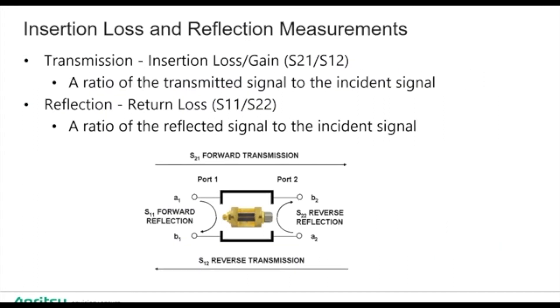As a reminder from our VNA fundamentals webinar a couple weeks ago, we have insertion loss and reflection measurements. Transmission measurements are forward S21 and reverse S12. Reflection measurements, return loss, are S11 and S22. Our little picture at the bottom gives you an idea of what those are.